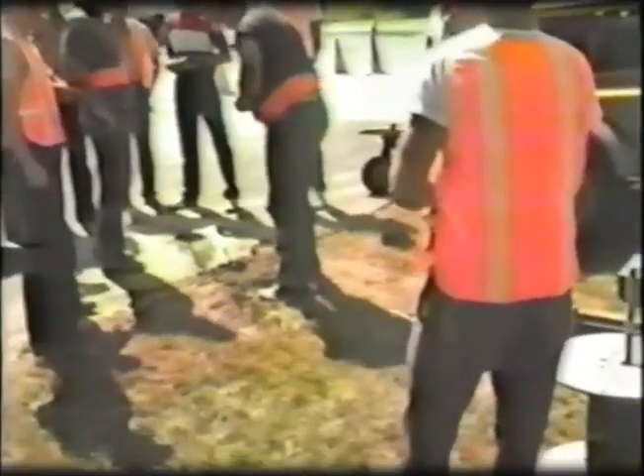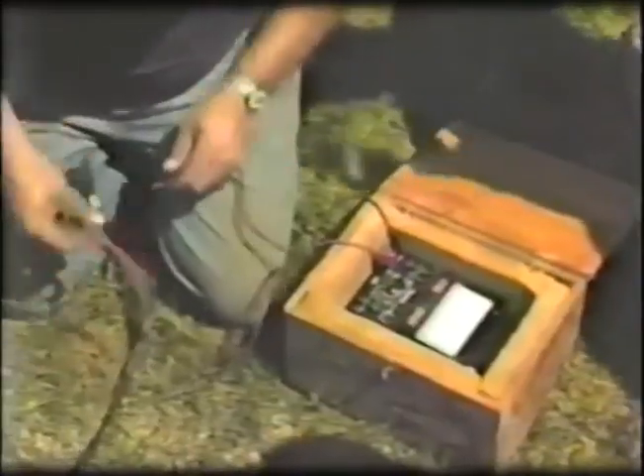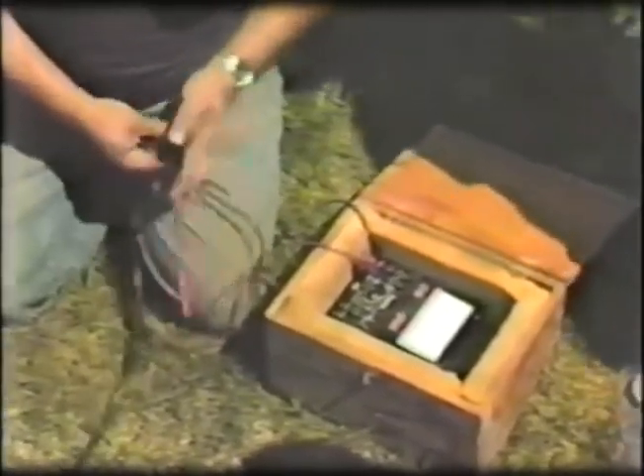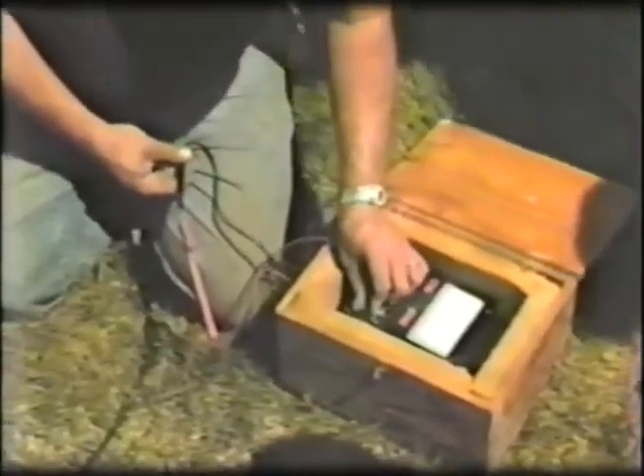Once the proper number of wire loops are in the slot, the wire's two ends are wound together for the specified number of twists per foot. They are then threaded through a conduit into a pull box, where an electrical inspection is performed and recorded. This includes measurements for leakage to ground, loop resistance, correct inductance, and induced voltage.